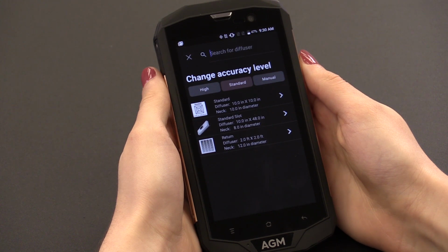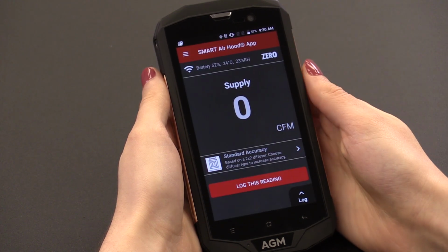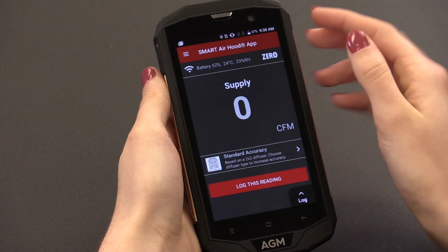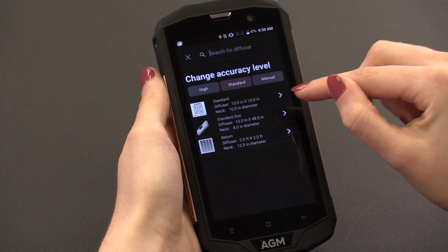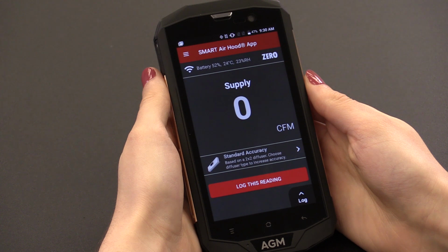We've included the 14 most common diffuser styles our users have experienced in the field and combined them in the supply option. These include 4-way, black, and several others. The slot option should be used when there is a slot or a linear in a branch. This should be selected when you are balancing with any of our skirt adapters, such as our 1x4, 1x5, or 2x4.